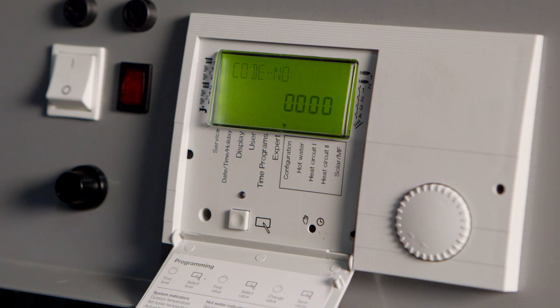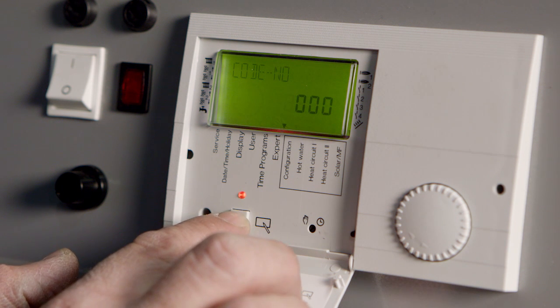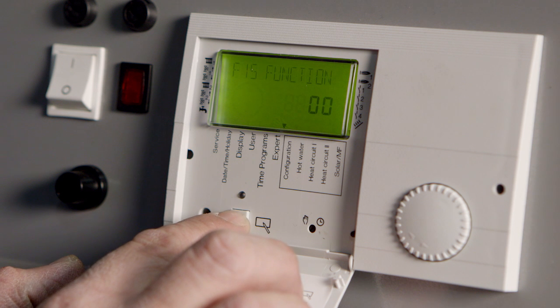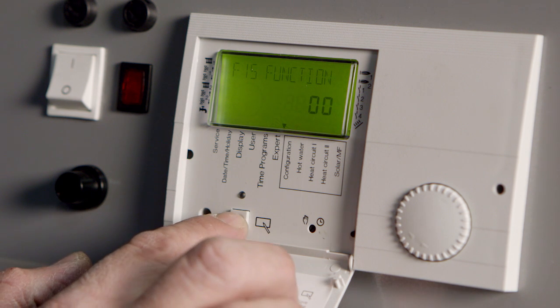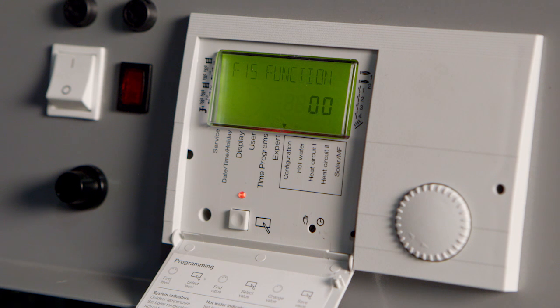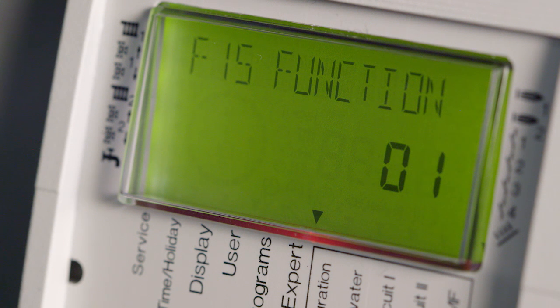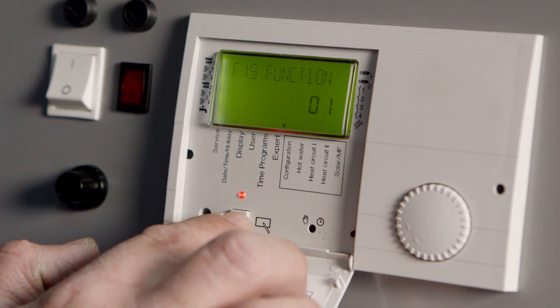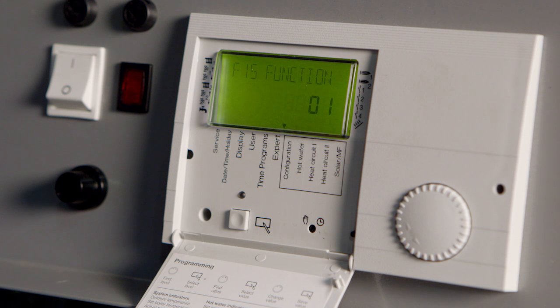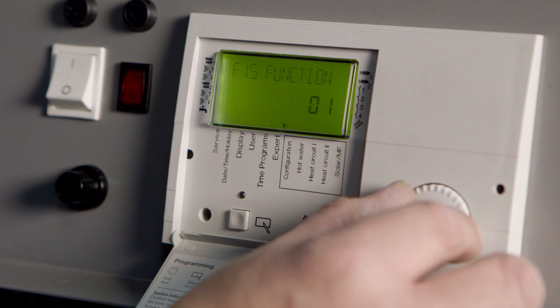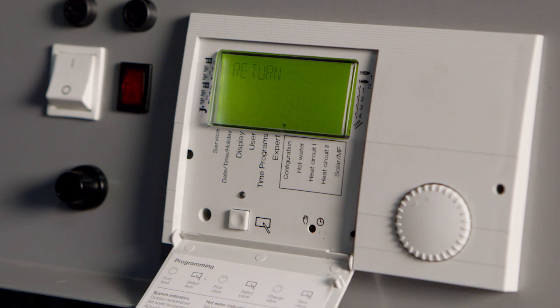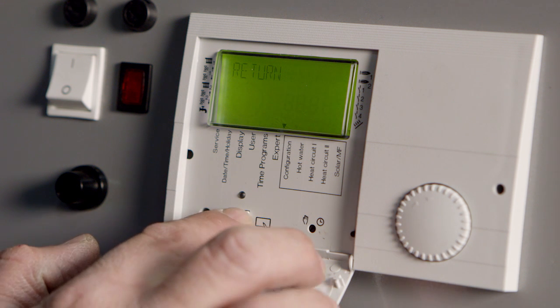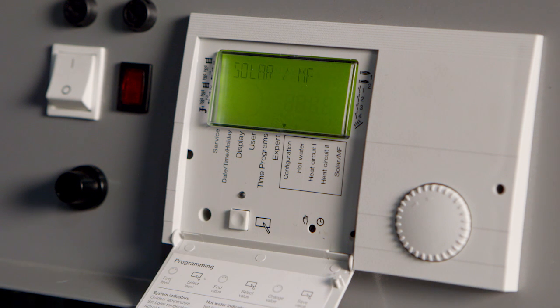Press the program key to change the function. The display will show that a code number must be entered. Enter 4 zeros by pressing the program key 4 times. Press a 5th time to continue. Press the program key. With the F15 function displayed and the red light lit, turn the rotary knob to change the F15 function to 01. Press the program key again to store the setting. Continue scrolling through the submenu until you find Return. Press the program key, which will allow you to exit the Solar/MF submenu.